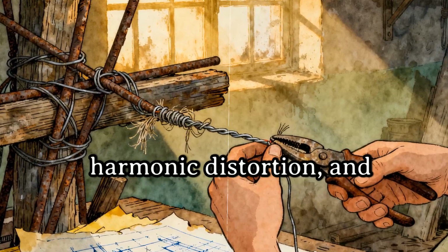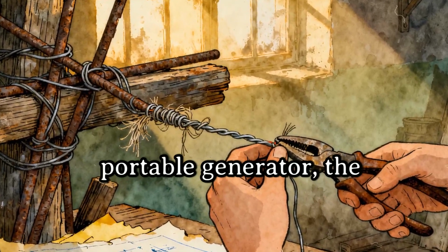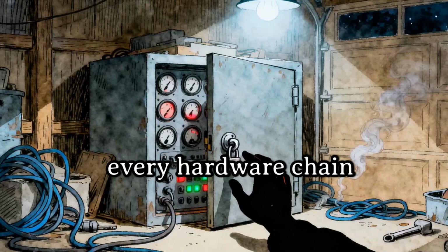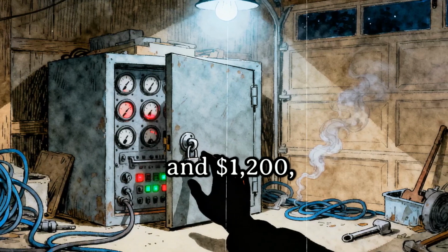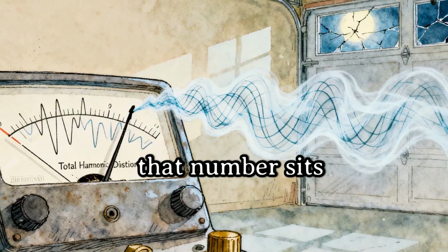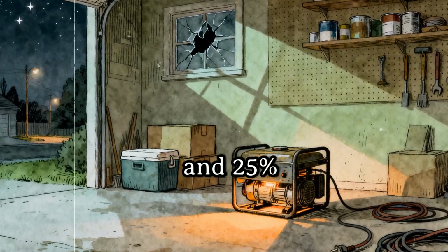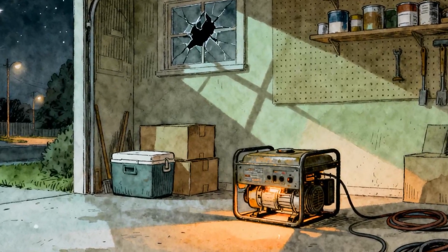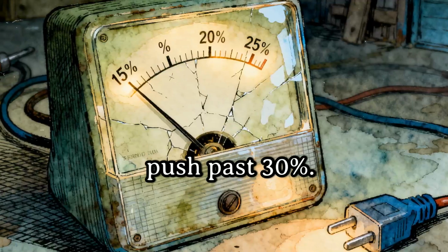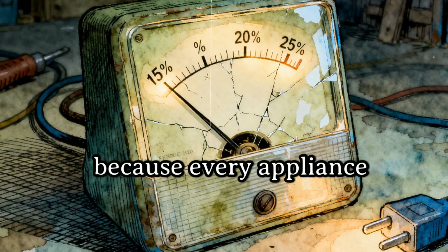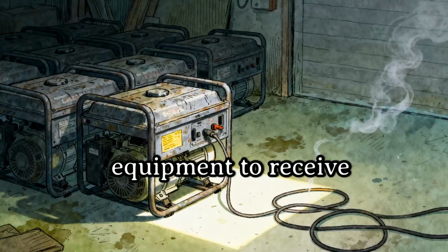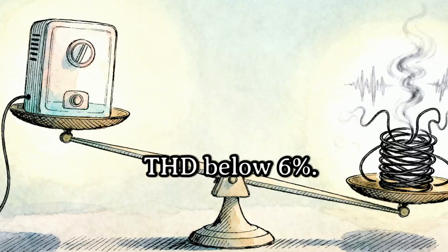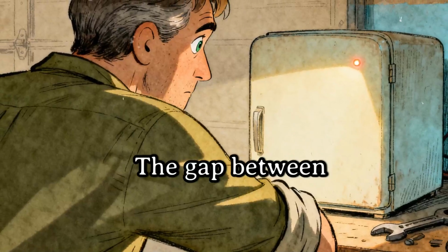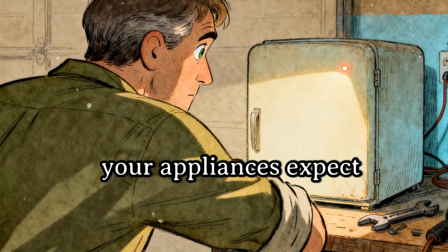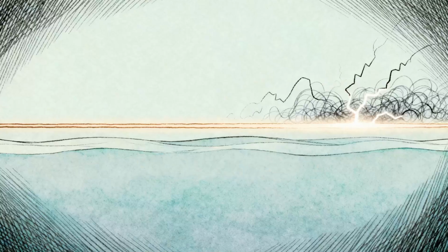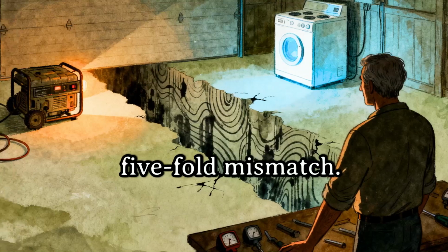It's called total harmonic distortion, and on a conventional portable generator, the kind sold at every hardware chain for between $500 and $1,200, that number sits between 15% and 25% under load. Oddly, some cheaper units push past 30%. The number matters because every appliance manufacturer designs their equipment to receive power with a THD below 6%. That's the threshold. The gap between what your generator produces and what your appliances expect is not a minor variance. It is in many cases a 5-fold mismatch.